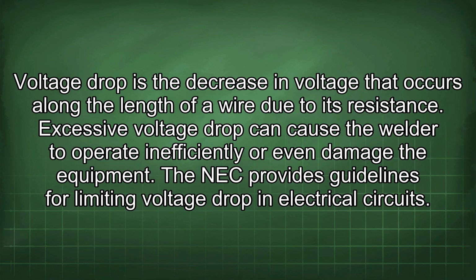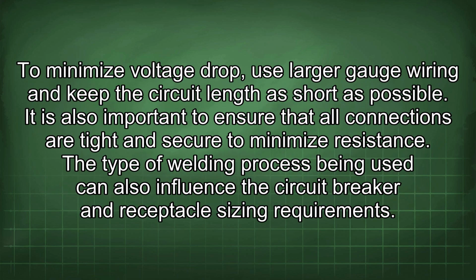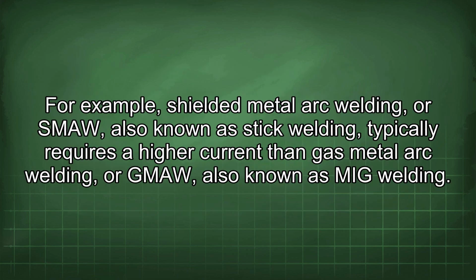The NEC provides guidelines for limiting voltage drop in electrical circuits. To minimize voltage drop, use larger gauge wiring and keep the circuit length as short as possible. It is also important to ensure that all connections are tight and secure to minimize resistance. The type of welding process being used can also influence the circuit breaker and receptacle sizing requirements. For example, shielded metal arc welding, or SMAW, also known as stick welding, typically requires a higher current than gas metal arc welding, or GMAW, also known as MIG welding.